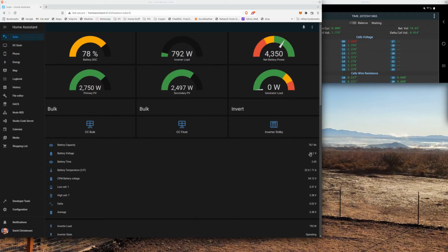But if we don't use enough energy before the batteries get topped off with amp hours, this voltage will kick up to say 54.5 or 54.6. What happens then is the delta between the cells will rise, and that causes the batteries to get out of balance because they're getting close to being topped up.